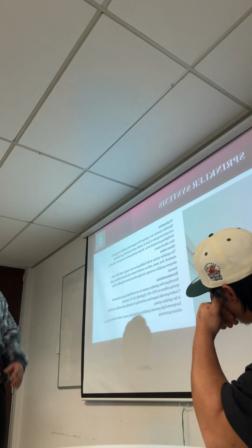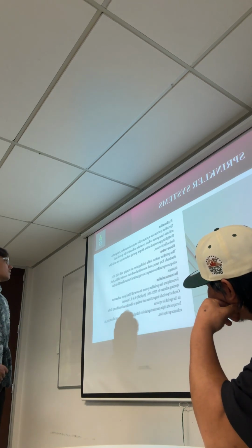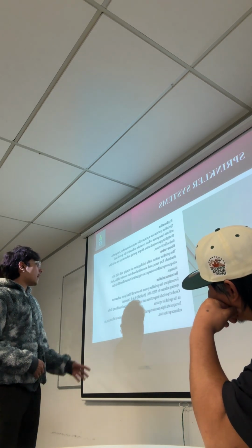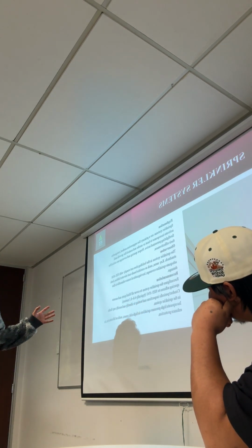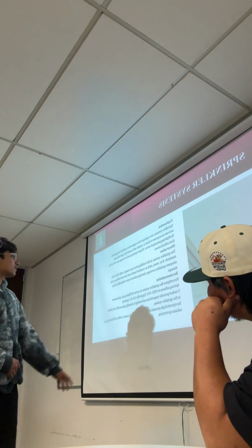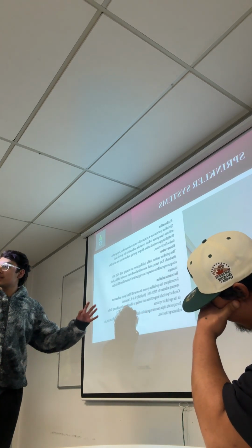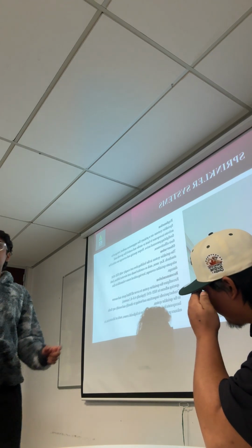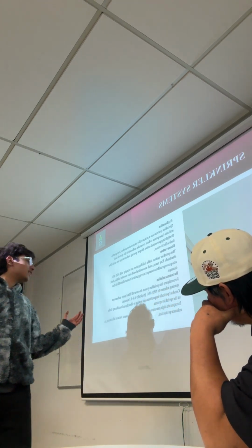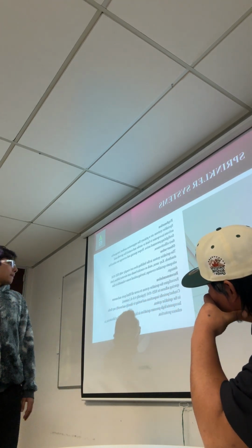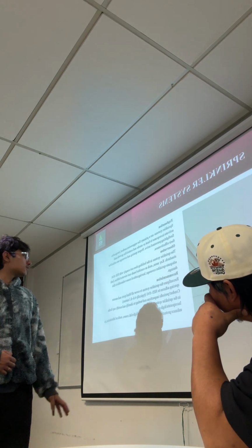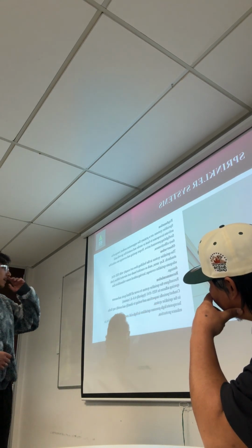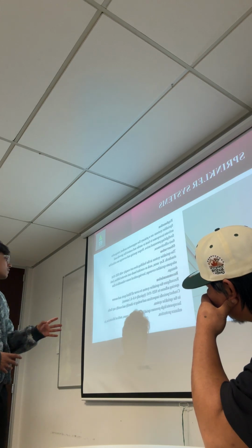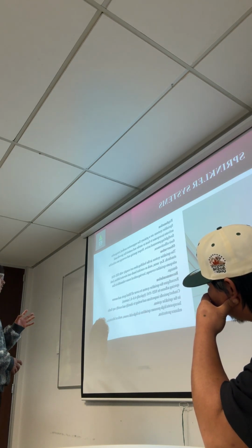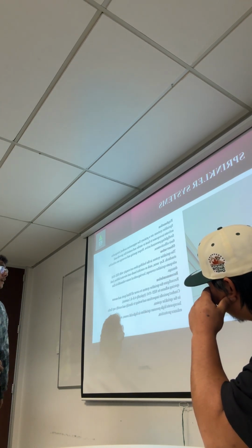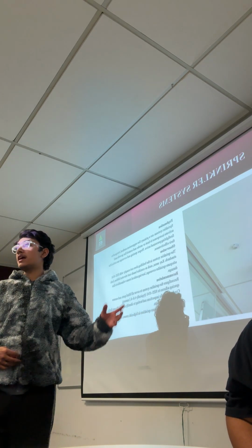So the sprinkler system should be reconfigured to cover all blind spots and ensure spacing adheres to the standard. Periodic inspection and testing should be conducted to identify and rectify any faults in the sprinkler system. High pressure sprinklers should be incorporated in high risk zones such as laboratories to enhance protection where fire is likely to happen.